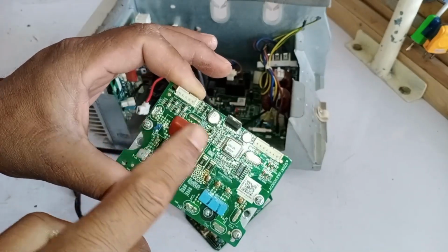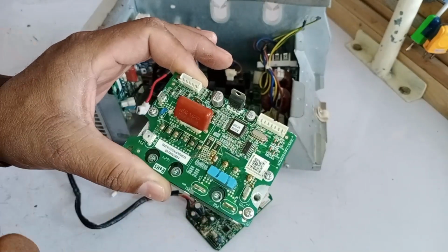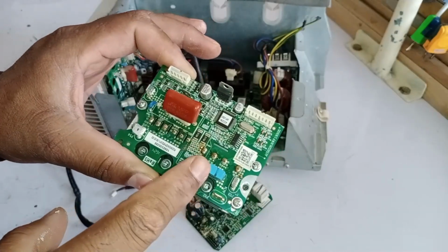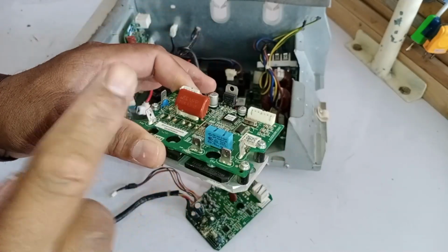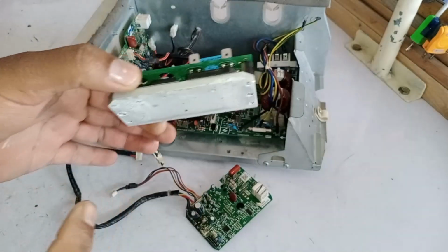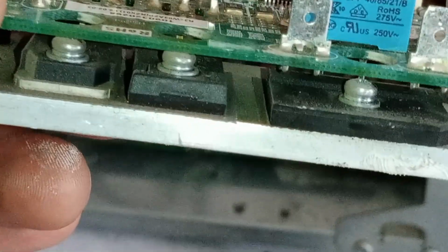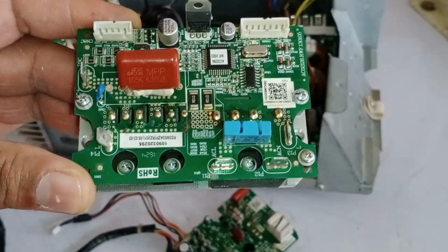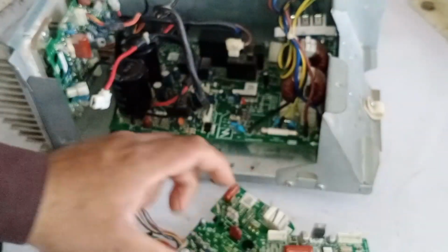If any small component like a resistor or capacitor becomes faulty, it will require checking each point one by one to identify the issue. However, at this point, we have confirmed that the rectification system, IGBT, and diodes are all working properly, so we can rule them out as the source of the problem.